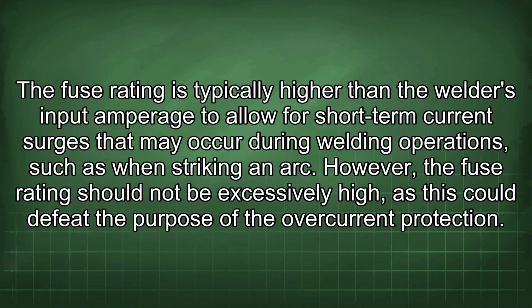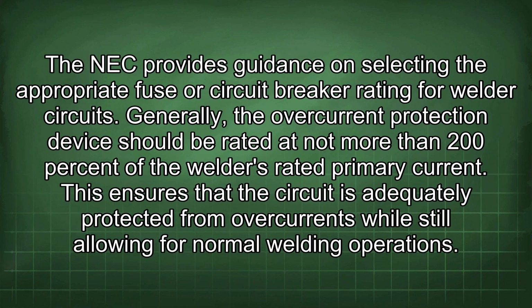However, the fuse rating should not be excessively high, as this could defeat the purpose of the overcurrent protection. The NEC provides guidance on selecting the appropriate fuse or circuit breaker rating for welder circuits. Generally, the overcurrent protection device should be rated at not more than 200% of the welder's rated primary current. This ensures that the circuit is adequately protected from overcurrents while still allowing for normal welding operations.